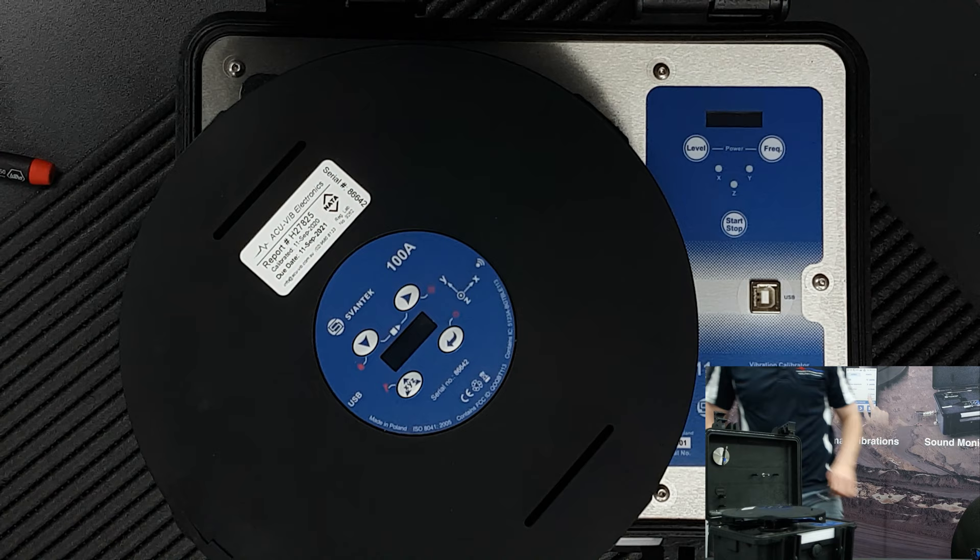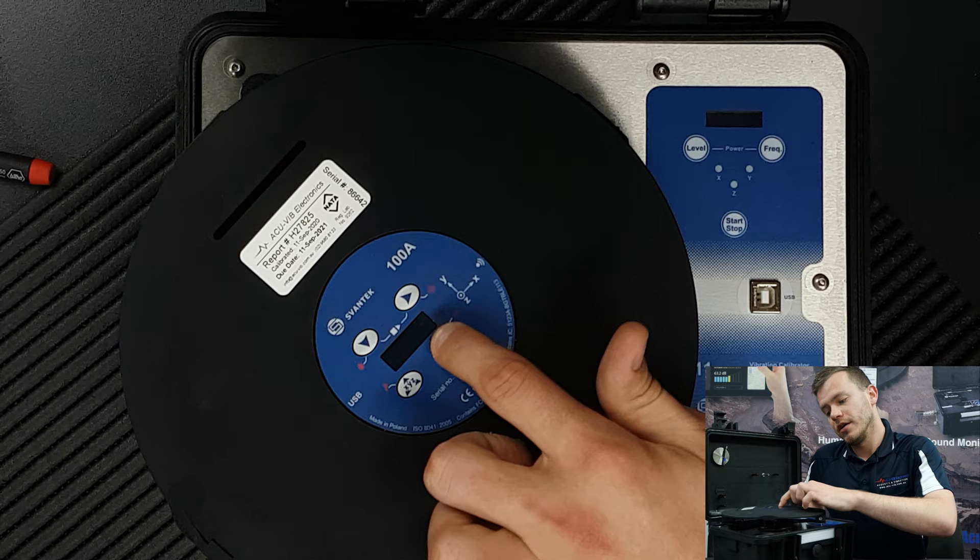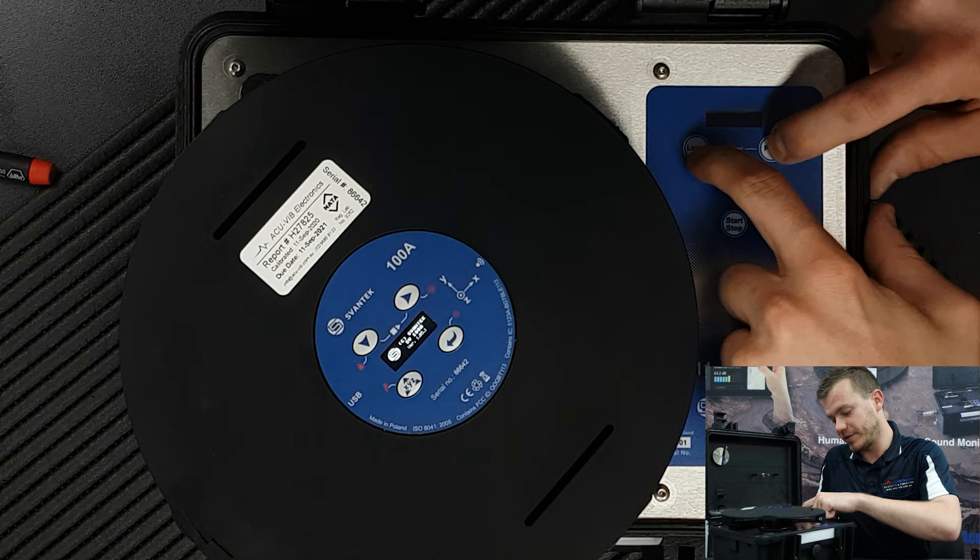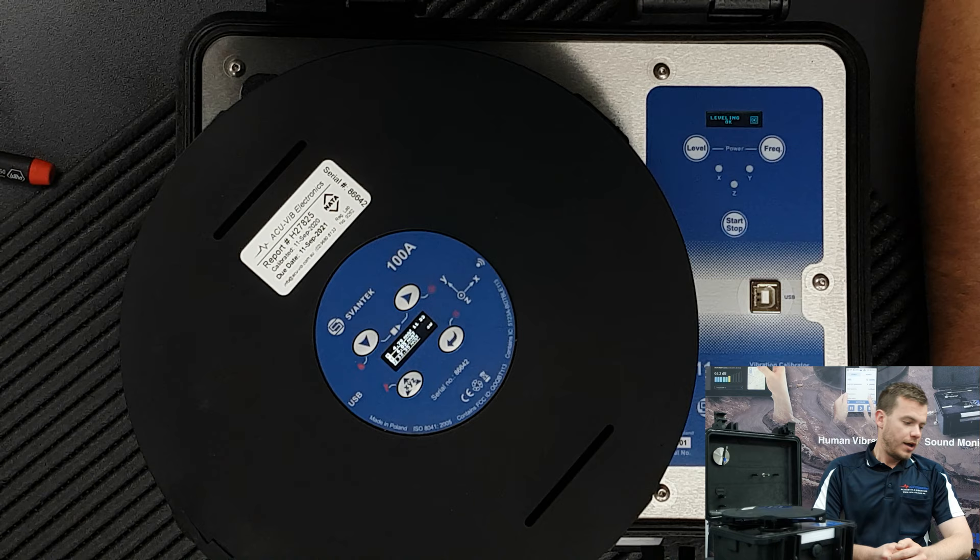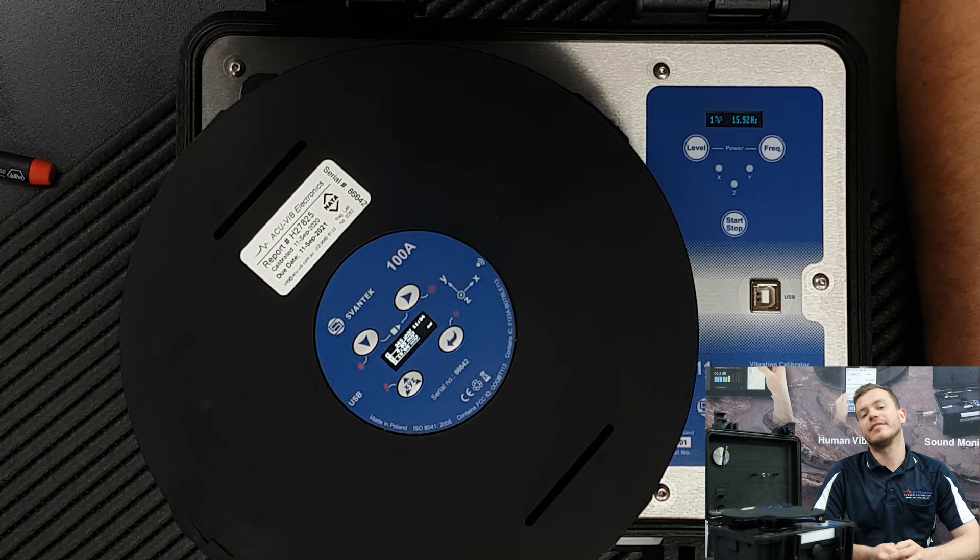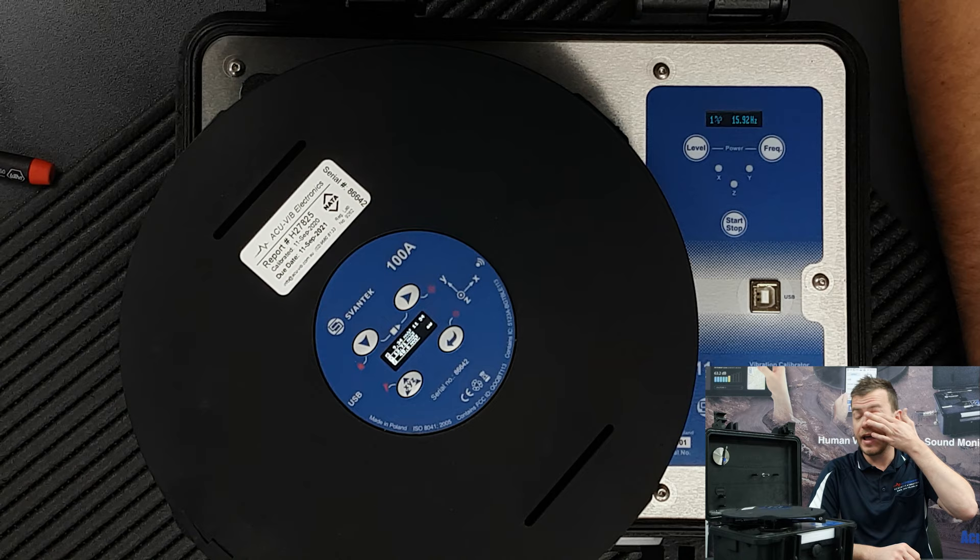What I'm going to do now is switch on the SV100A and also switch on the shaker itself. To turn it on we just press the level and frequency button together and release. It's going through its warm-up. Based on calibrated levels and frequencies for the whole body X, Y, and Z axis, we are going to do 1 meter per second at 15.92 hertz.